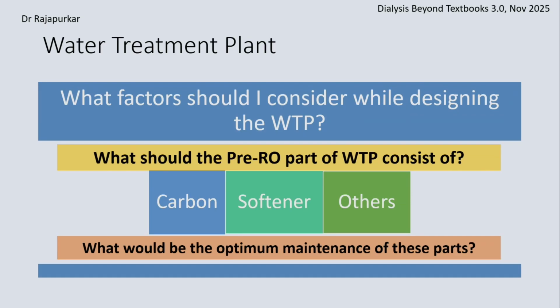And then I'm saying that every day, if you take out the time for sterilization, time for cleaning, and the time when it is going to remain idle, you calculate for 16 to 18 hours a day, and then double that with your capacity. Why double it? Because as and when there is a maintenance problem or your water treatment system needs some maintenance, then your system should not go down and your dialysis should continue. So that is the quantum of water you require. So based on that, you design your...